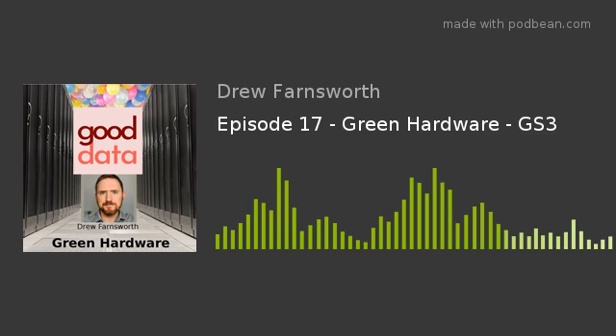And we're back. Eliminate 120 volts UPS. Okay, so here's another little soapbox about small data centers or anything that really operates on a 120 volt feed. The problem with a 120 volt feed is that a UPS that's built on 120 volts is inherently less efficient by a whole lot than something that is built on a 480 volt or 208 volt three-phase topology.